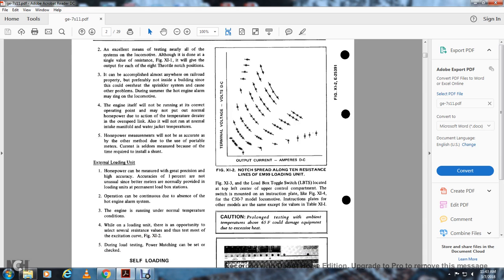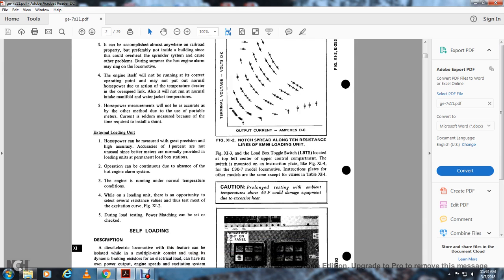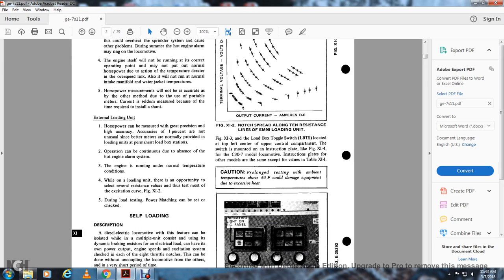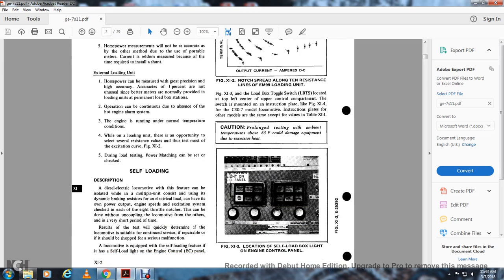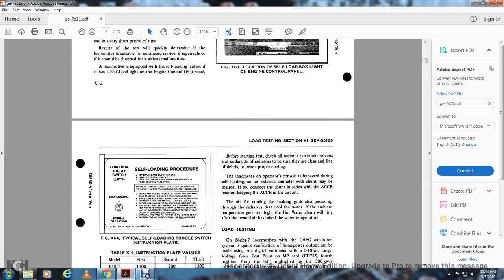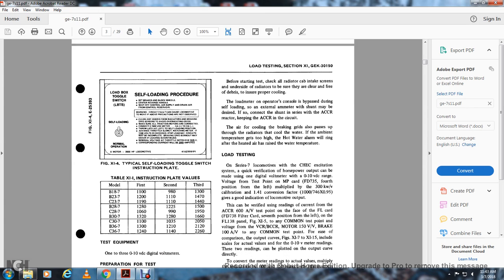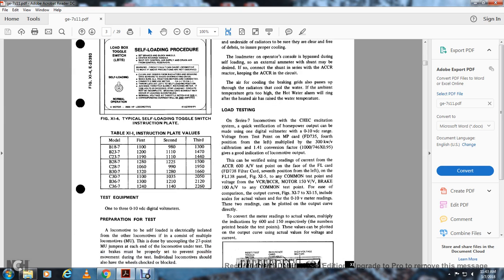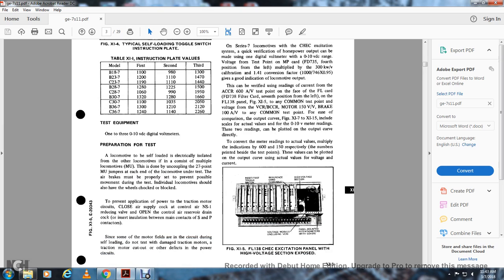Caution: prolonged testing with the ambient temperature above 65 degrees could damage the equipment due to excessive heat. Figure 11.3: location of the self-loading box light on the engine control panel, indication of the light on the engine control panel. Figure 11.4: typical self-loading toggle switch instruction plate, load box toggle switch, self-loading normal operation, self-loading procedure. Table 11.1: instruction plate values, model first, second, and third. Testing equipment: one 0 to 10 volt digital voltmeter.